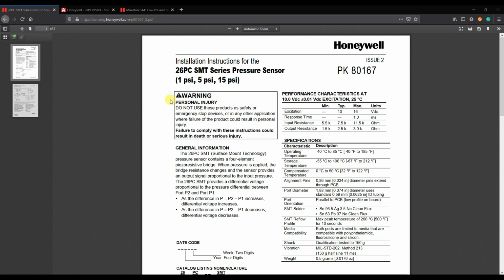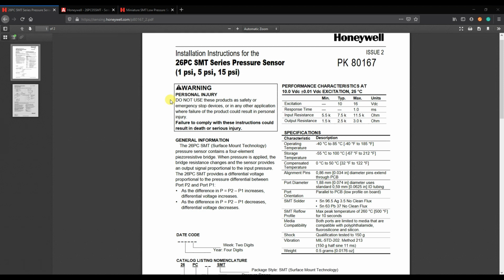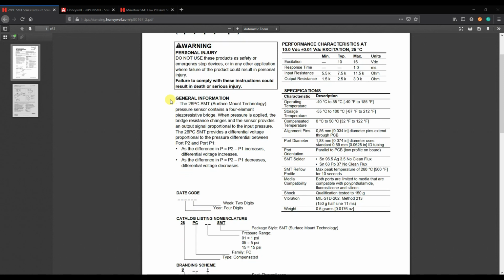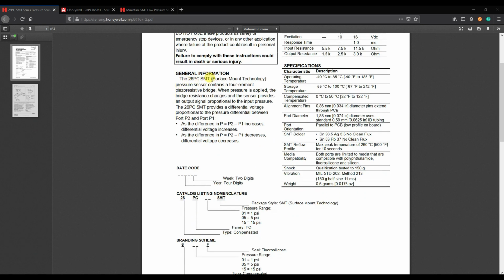Don't use these products as safety or emergency stop devices or in any other application where the failure of the product could result in personal injury. So please use it at your own risk. The general information about this sensor: the sensor is SMT, aka Surface Mount Technology. It uses a piezoresistive bridge in a Wheatstone bridge configuration. So when pressure is applied, the bridge resistance changes, and the sensor provides an output signal proportional to the input pressure. Therefore, there is a differential voltage proportional to the pressure difference between port 2 and port 1. Here I am going to use port 2 to measure the applied pressure, and port 1 as a reference pressure.